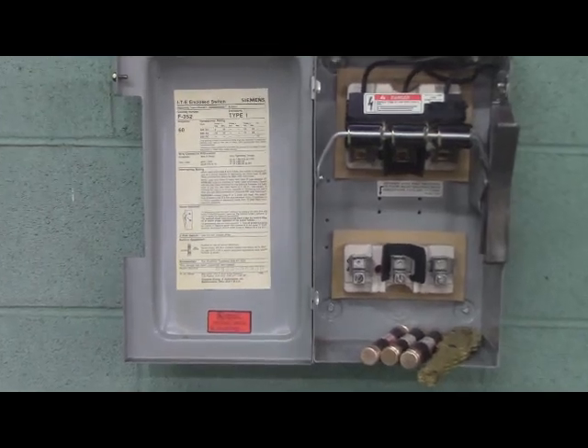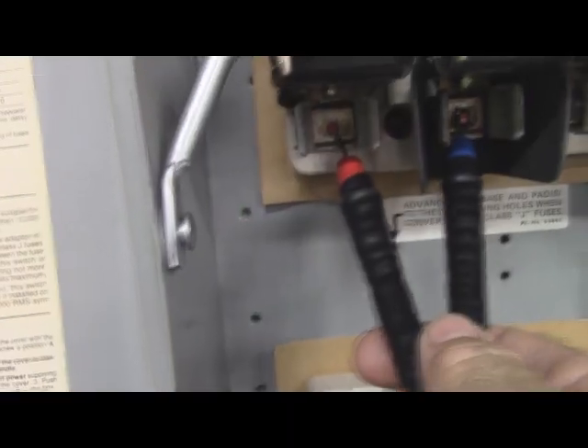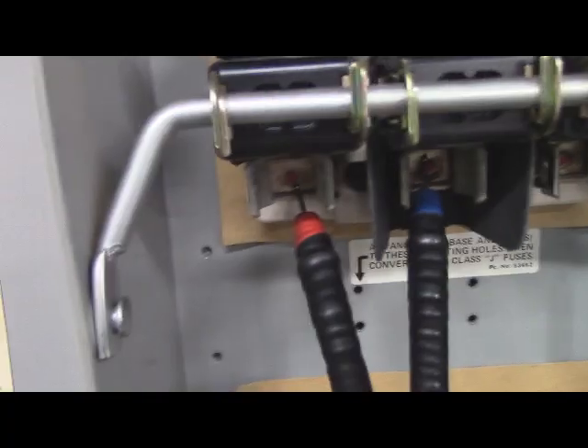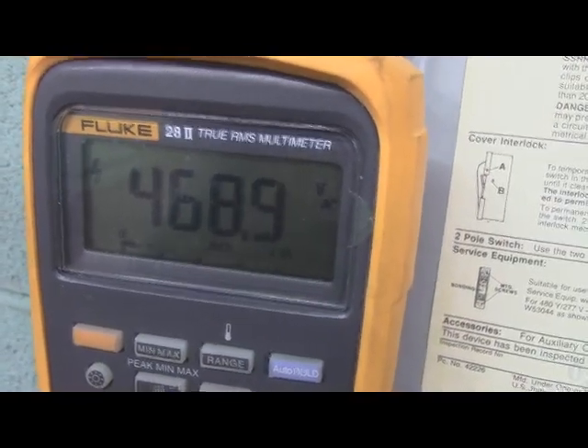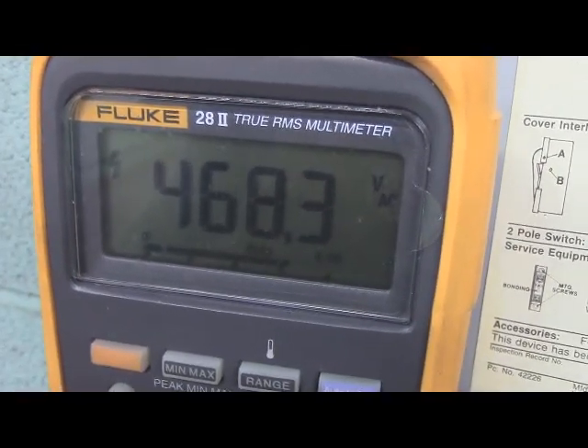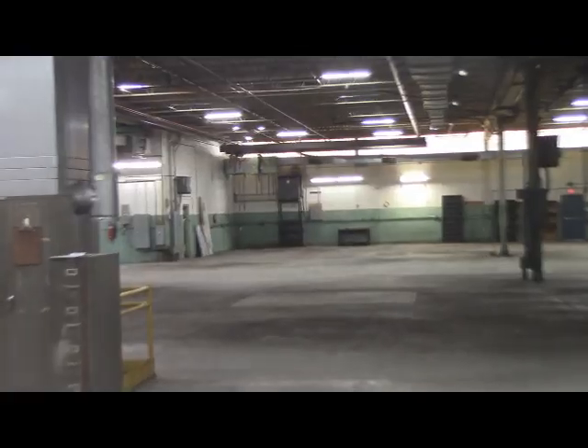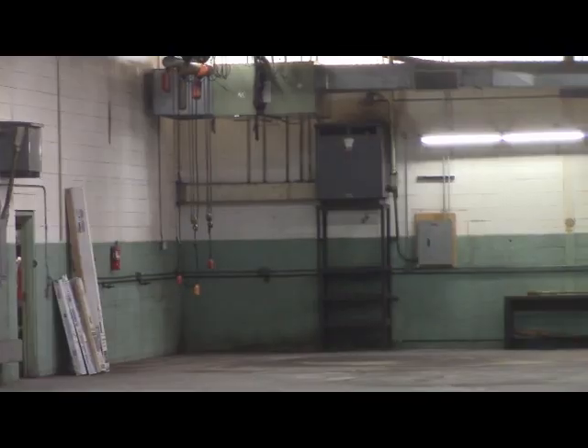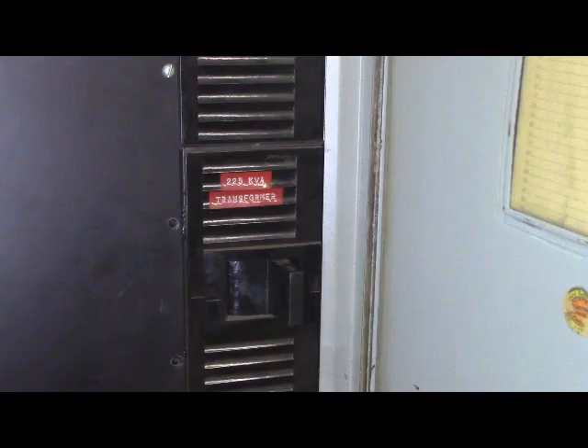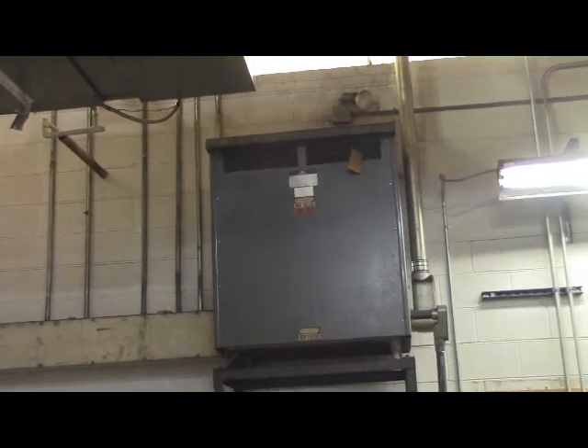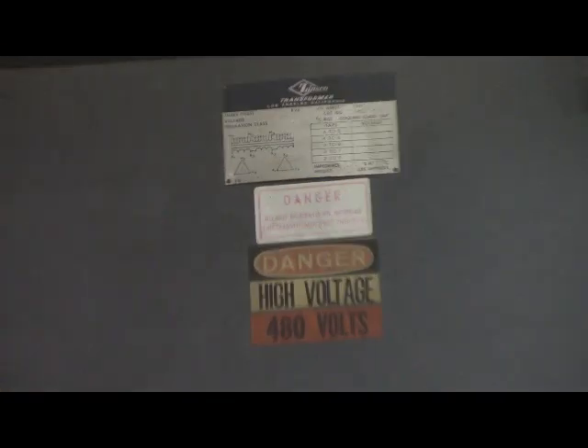Okay, this cutout switch is still energized. We're going to disconnect this. There's construction going to be going on pretty soon. We don't need this energized out here. About 120 feet away is a 225 kVA transformer supplying it, and a couple other boxes like this one. We're going to cut that transformer out by turning off a 400 amp circuit breaker in the distribution room near it. That'll make all of these areas much safer to work on.